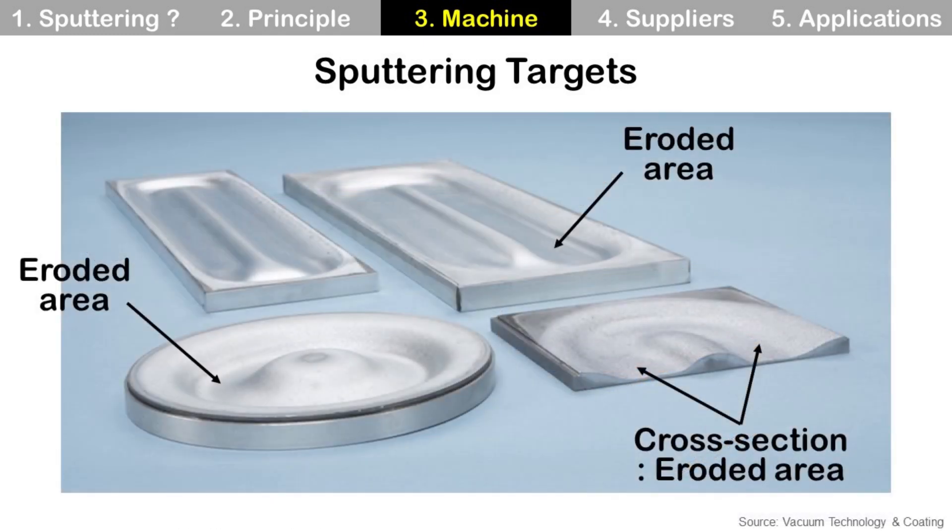As I mentioned before, argon ions eject target material, so after some use, targets look like this. We can see eroded areas on the target surface which are ejected by argon ions. At the right, we can see the cross-section and understand how much material has been ejected.